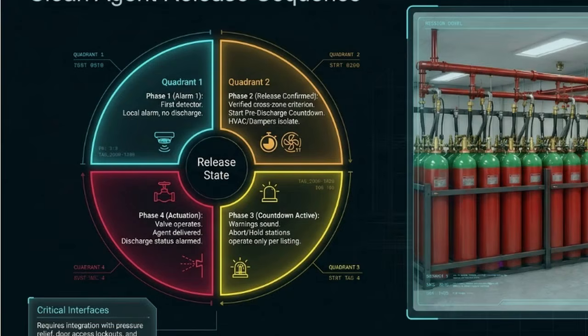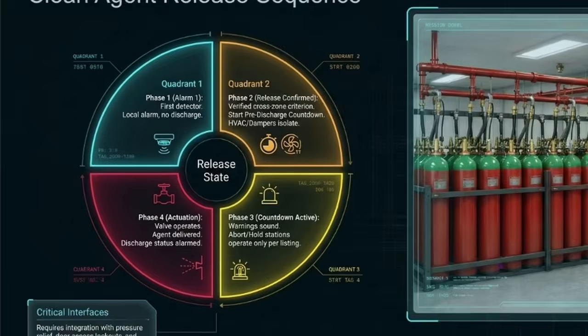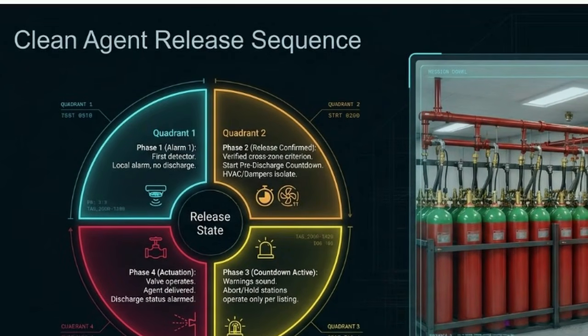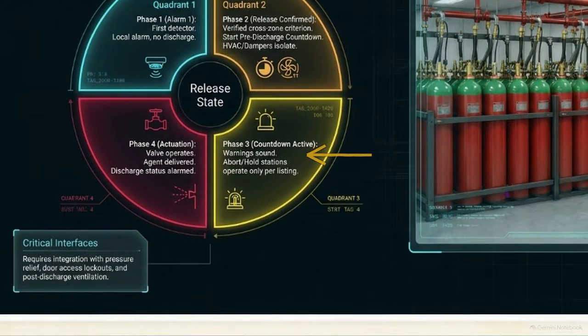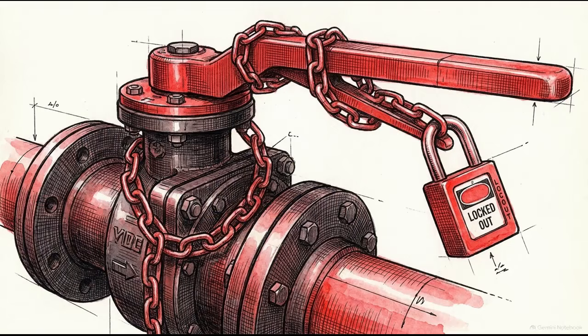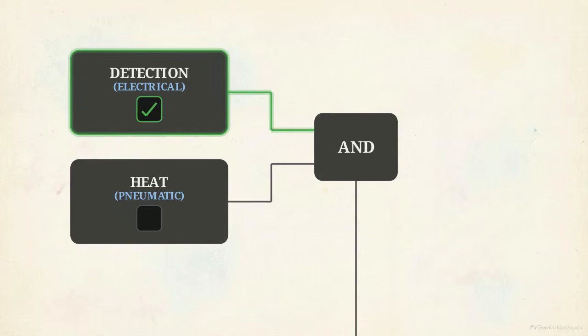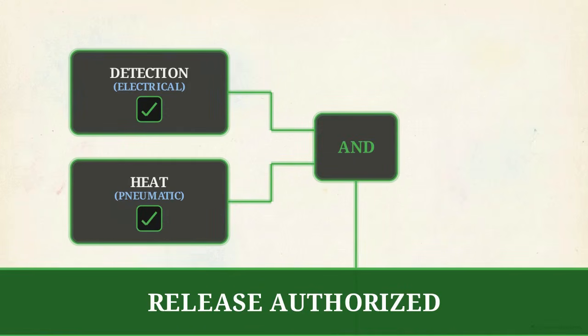piping. For gas suppression, this circular diagram breaks down the four-quadrant clean agent release sequence. It moves systematically from the initial local alarm in Phase 1 through verification to physical actuation in Phase 4. During Phase 2, the verified cross-zone criterion starts the pre-discharge countdown. Critically, this phase isolates the HVAC and dampers to seal the room. Phase 3 activates the warnings, and abort stations can pause the release, but only according to their strict equipment listing. The physical suppression hardware remains firmly locked in a safe state until the digital state machine provides absolute dual-factor verification that a fire actually exists.